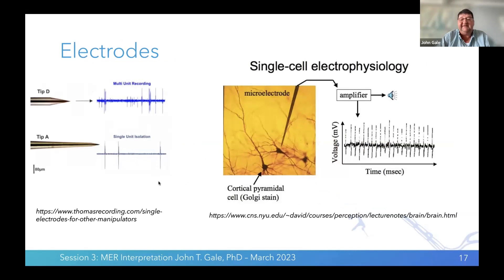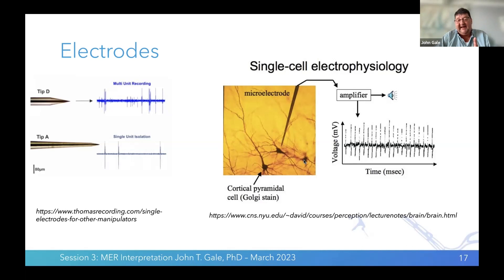Getting back to impedance: here are two different tips with two different impedances, showing how the microelectrode looks in the brain. The tip of one contact is roughly about 30 microns on a typical DBS microelectrode. The closer you are to a neuron, the higher the signal will be. A neuron that's further away will show a smaller spike. Neuron diameters are approximately 15 to 18 microns — so our contact is roughly the size of the neuron or double.